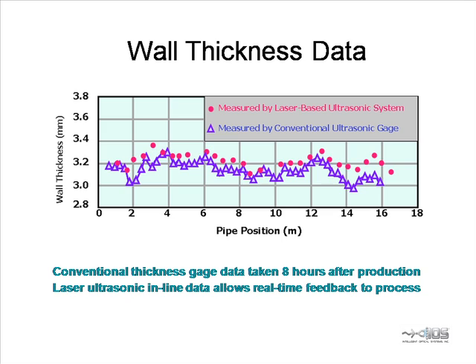Here we have plotted the data as wall thickness versus position along the 16-meter tube. The laser ultrasonic data is plotted in red circles. After the tube cooled, thickness data was taken by hand using a transducer-based thickness gauge, plotted in violet triangles. The data are in good agreement after accounting for an expected offset associated with thermal expansion.